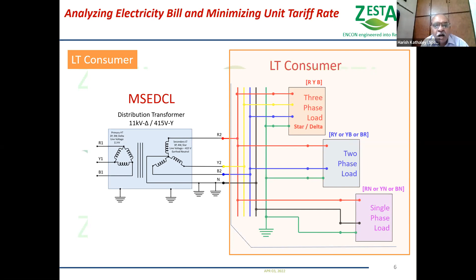Electrical input is voltage and frequency. Electrical effect due to our electrical loads is drawn current value, displacement power factor, harmonics, distortion power factor, and true power factor. I would like to emphasize we are not going to talk about harmonics and distortion factor right now, because in today's scenario we get directly true power factor in our meters, and Maharashtra board has not imposed any penalties for harmonics and distortion power factor.